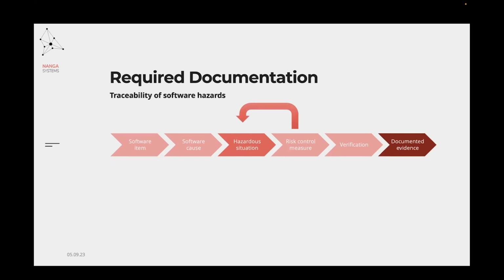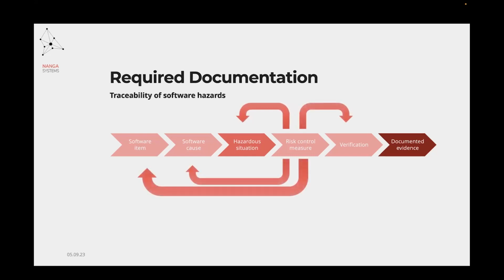And here we will make an assumption that we need to change one of our RCMs and we have to perform an impact analysis. In this case, we have to review if the hazardous situations that are linked to it confirm if the change is still suitable for these hazardous situations and assess if the risk control measure is still meaningful mitigation for the software causes that are traceable to the hazardous situation. The verification might change depending on how the change affects the software items. For example, a range check that's the same risk control measure might be something that affects software items differently.